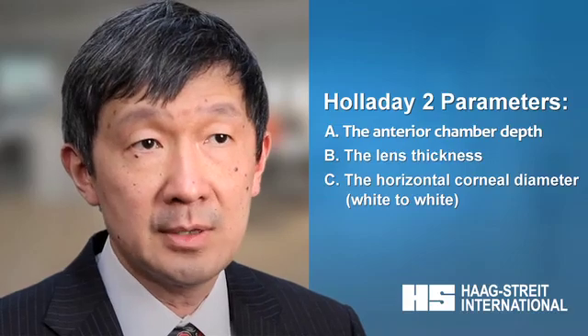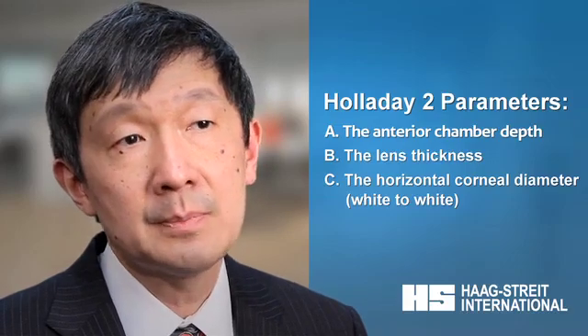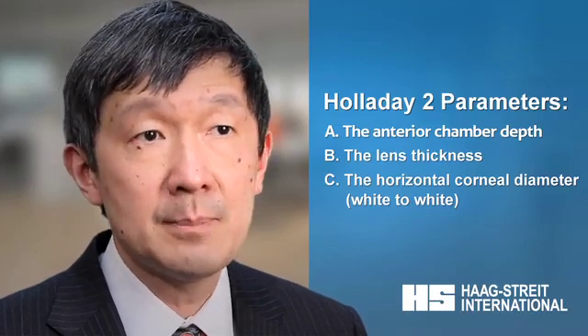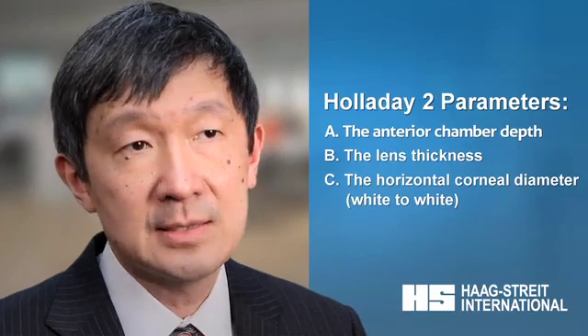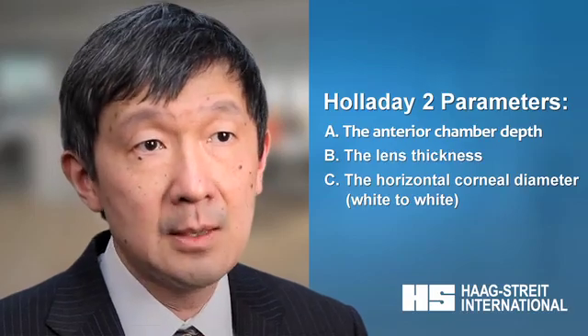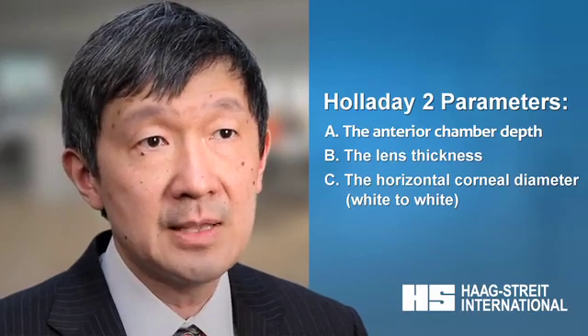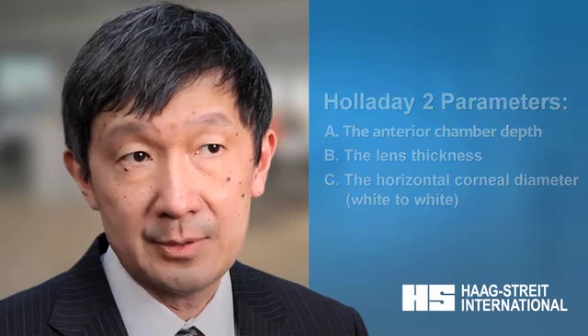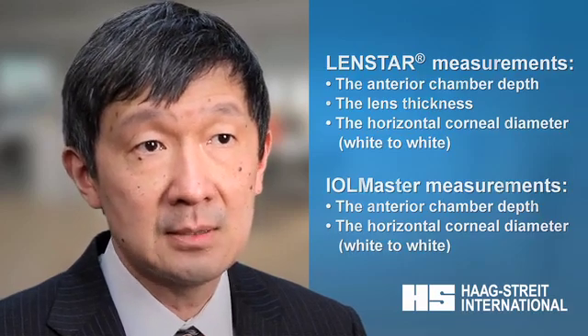The horizontal corneal diameter, also known as white to white. Currently the most common optical biometry units are the IOLMaster 500 and the LensStar. Both measure the anterior chamber depth and horizontal corneal diameter. One of the main differences between these two units is that the LensStar measures the lens thickness whereas the IOLMaster does not.